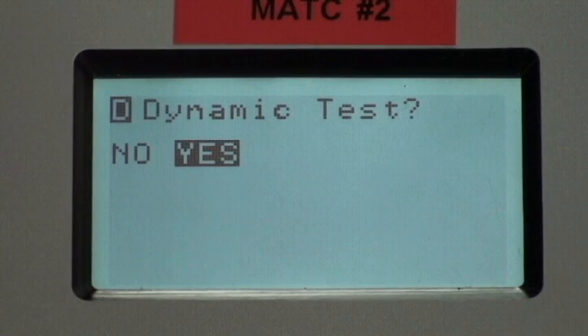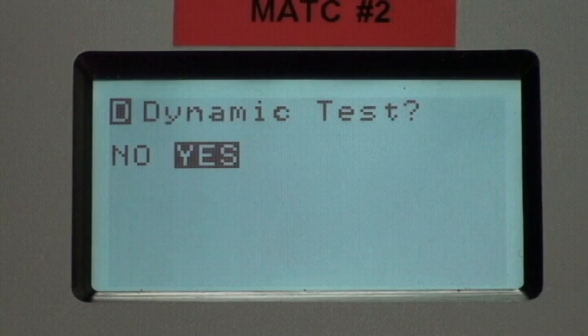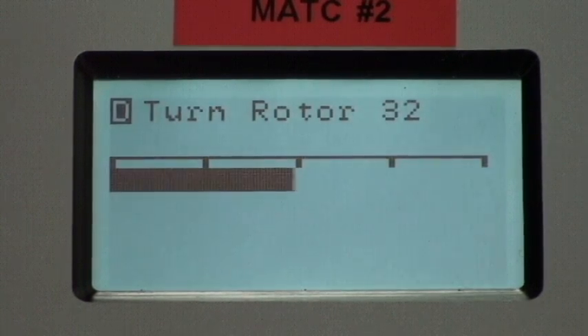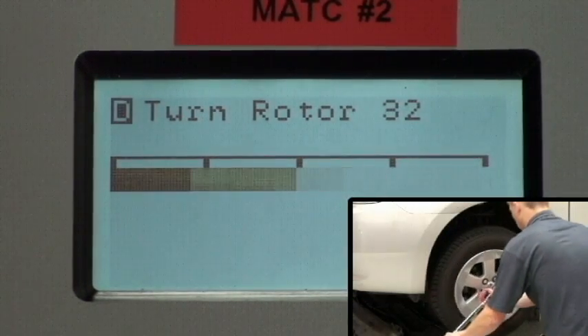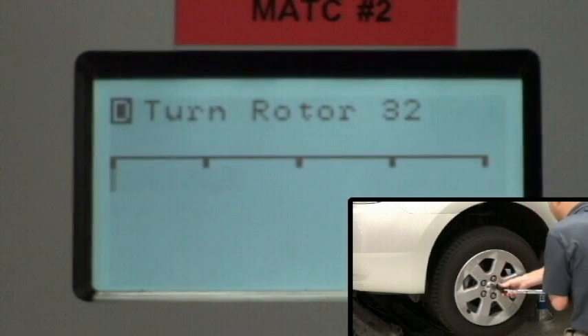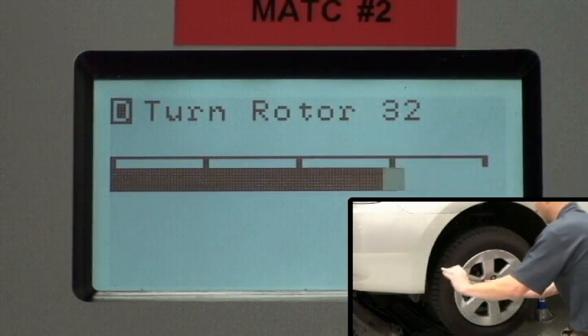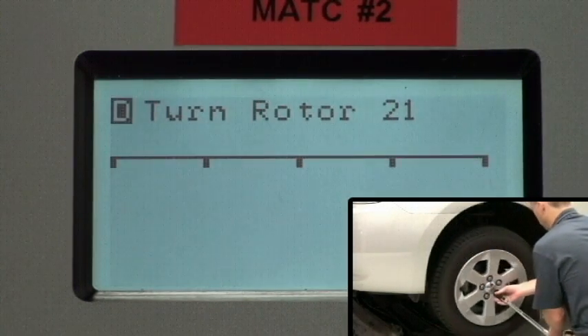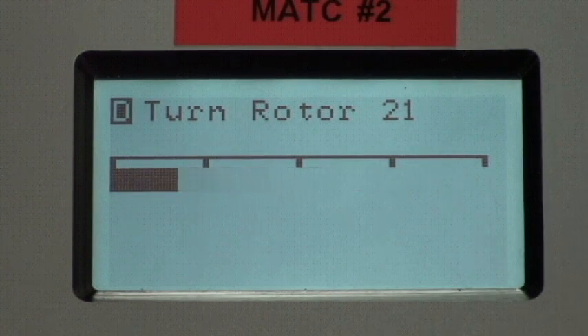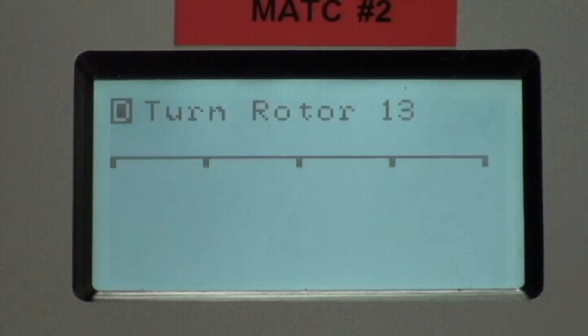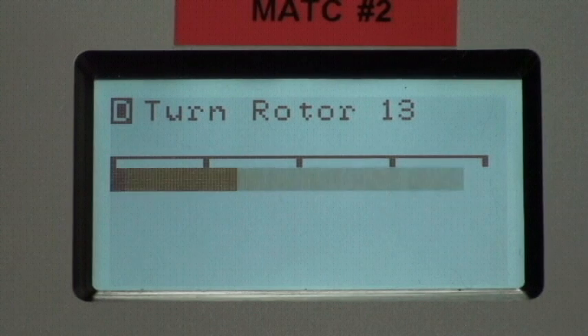When the static testing has been completed, the technician has the option of performing a dynamic test. The dynamic test requires that the motor or generator rotor be turned at a slow RPM so that a more precise stator test can be performed and a test of the rotor, permanent magnet rotor magnets, or the AC induction rotor bar state of health can be determined. Rotor turning is accomplished by turning one of the front wheels.